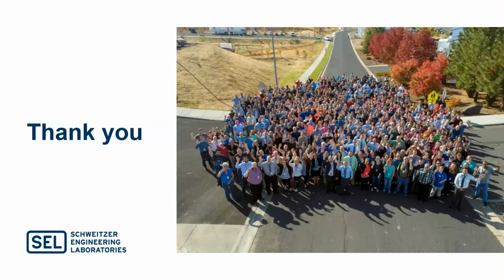Thank you. When you talk about seamless transition, what is your time frame? What is your expected time frame for the completion of that transition? The definition I put out there is seamless means your lights don't go out. So if you have an inverter-based resource with no inertia, no kinetic energy carry through, that means 4 milliseconds. It may not be fully achievable without very high-speed algorithms in a relay. If it's a large utility with many thousands of pounds of rotating steel on rotors acting as your kinetic energy storage, you still need to be fast because you can't run systems through faults, long periods.